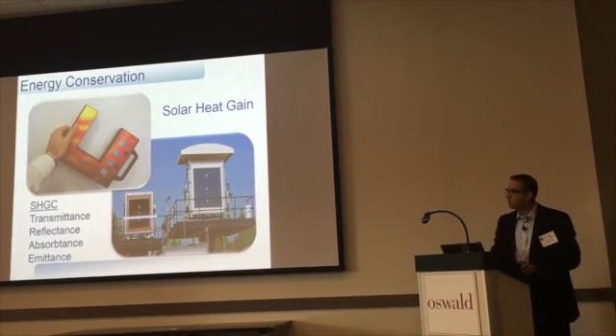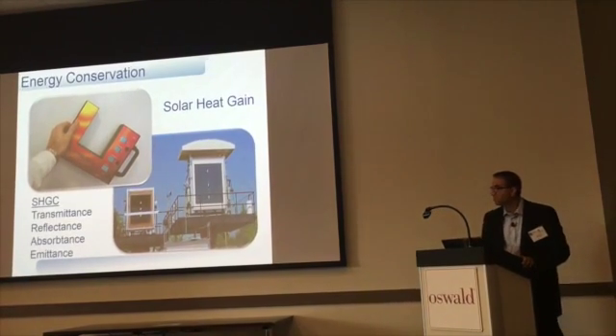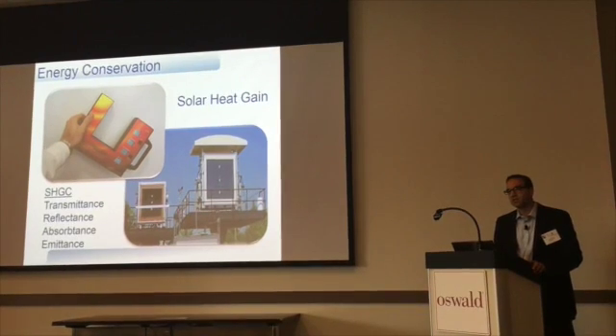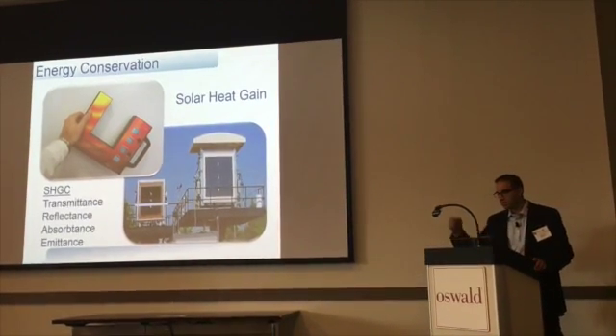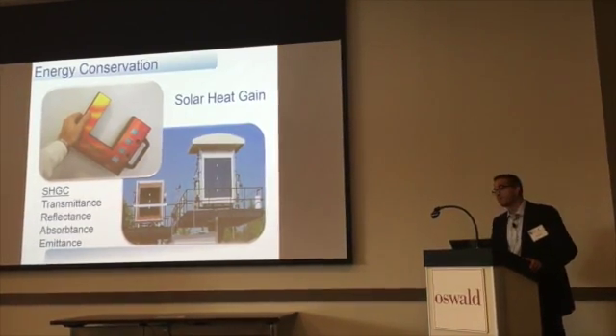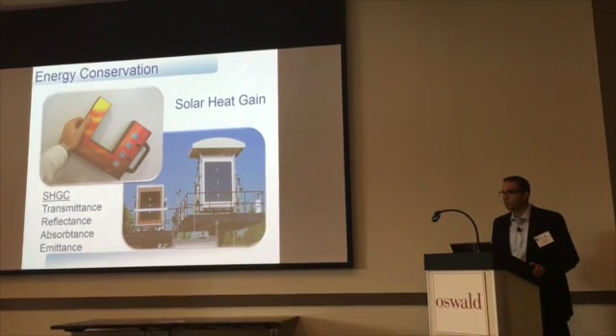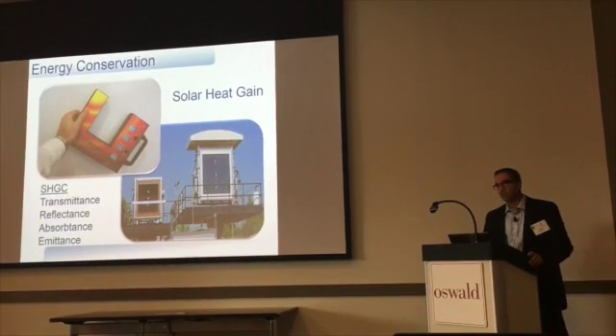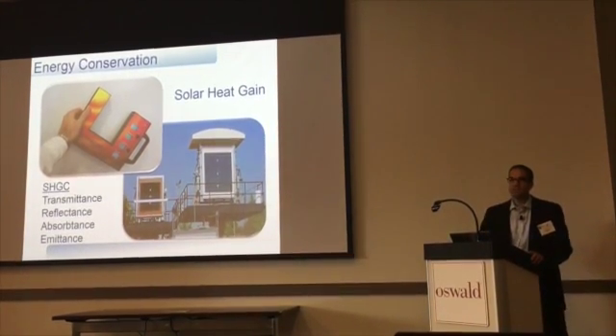Solar heat gain is a little obscure because you can't really see it. The gauge in the upper left is a tool you can use to measure the solar heat gain of an existing window. A lot of times we get involved in projects where the whole goal is changing out windows to save money in five years, and somebody has a magical computer program that spits out a five-year payback — but maybe the payback is three years, maybe it's 15. We want to be very careful that we have the right inputs. The programs are usually pretty good, but if we're putting bad data in, we can't expect the outputs to be correct. Understanding what the existing building's solar heat gain, air leakage rate, and U-factor are is hugely important to determine what the delta is with new performance.